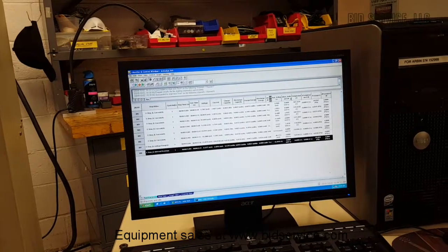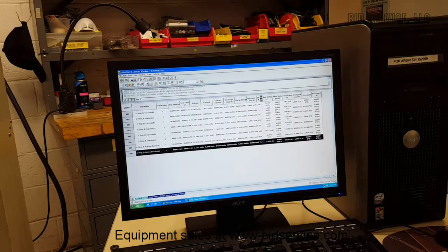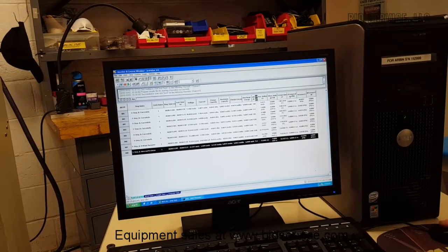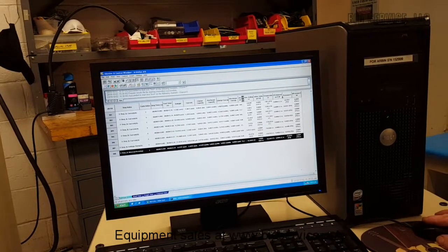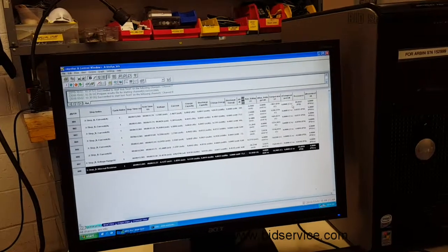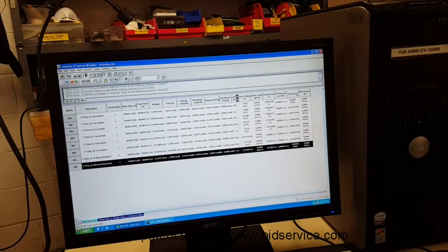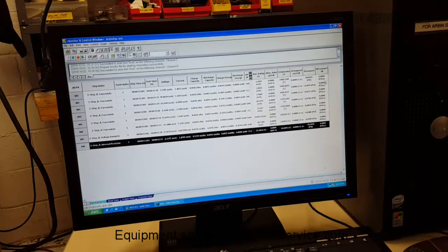Auxiliary voltage measurement, and then the rate of change of the voltage is displayed here, for example in millivolts per second. Our temperature reading, and then the rate of change of the temperature reading as well in degrees per second. Our pressure reading, and respectively the rate of change of the pressure reading during the duration of the test.